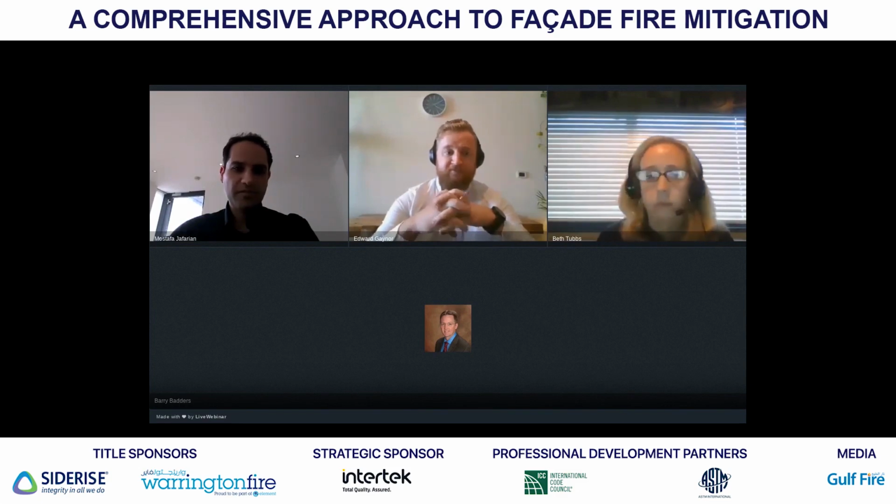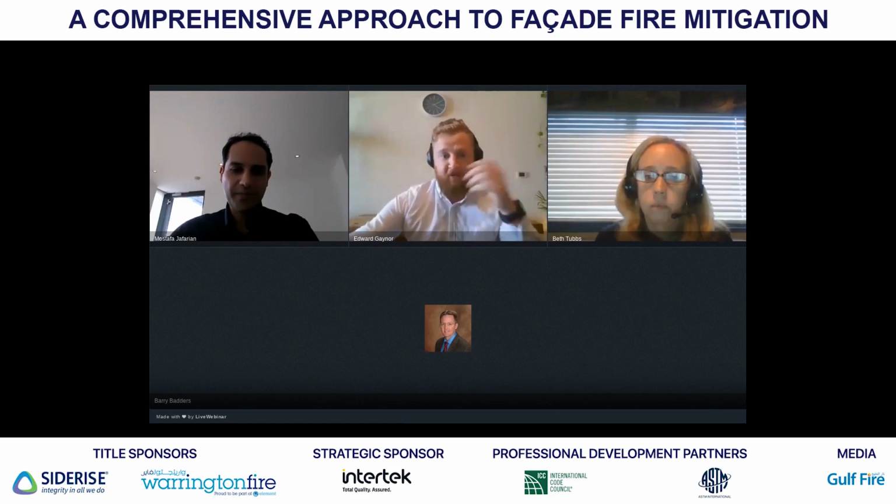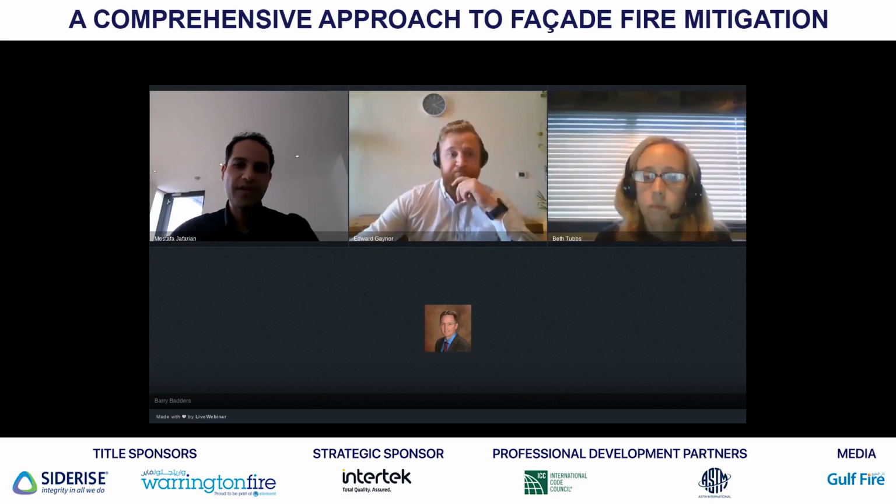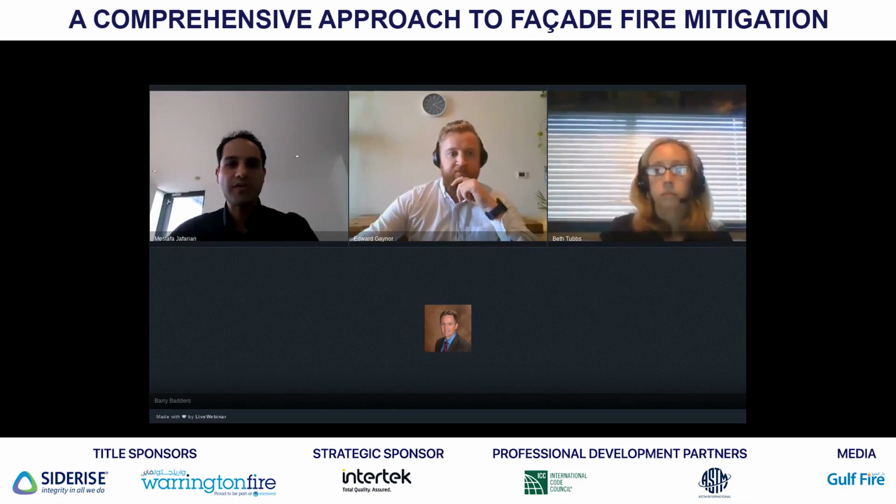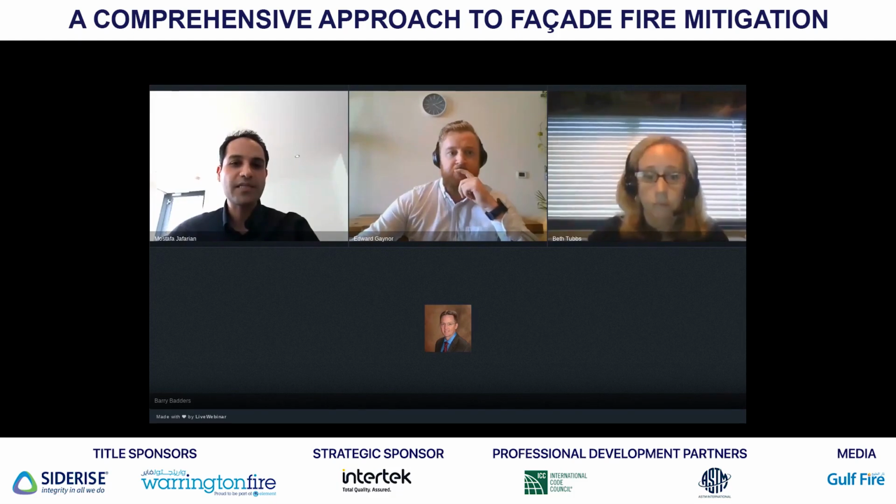This is Mostafa, and as you said, it's point of view rather than legislation. When it comes to facade, you're talking about the system, not a specific product. For instance, if you have a manufacturer who prepares the cladding on their own, an insulation manufacturer who provides the insulation, and a cavity barrier manufacturer who comes with the fixation of the cavity barrier, all of them are critical elements of the system when you are testing. If something goes wrong with the fixation of the cavity barriers, your system could easily get bypassed by the fire inside the cavity.